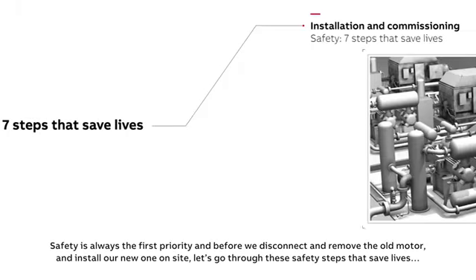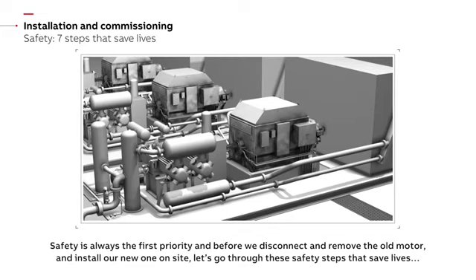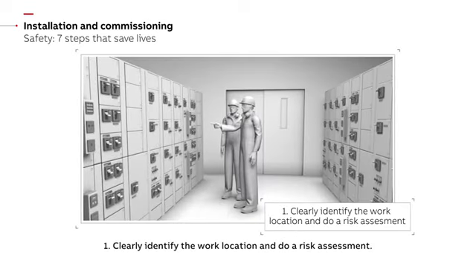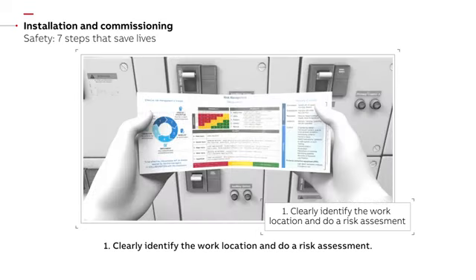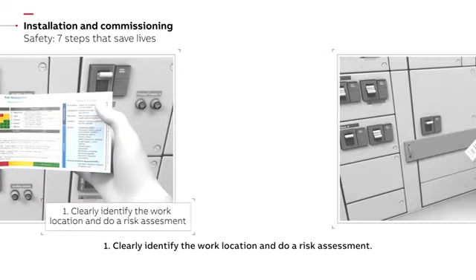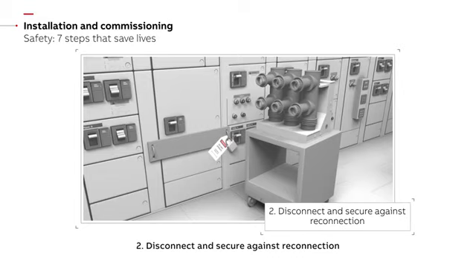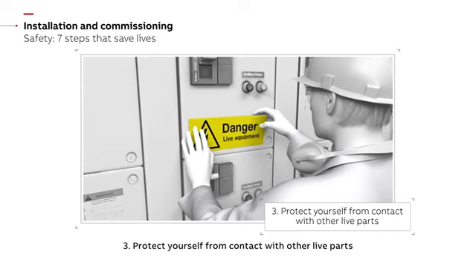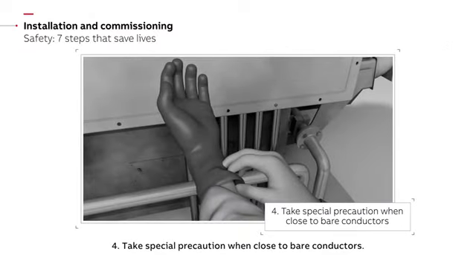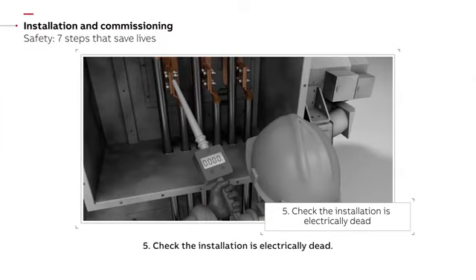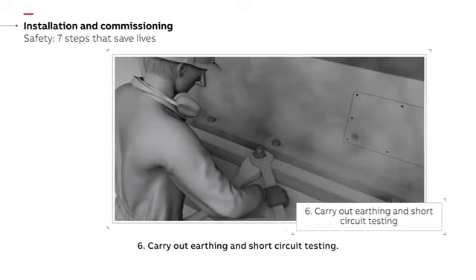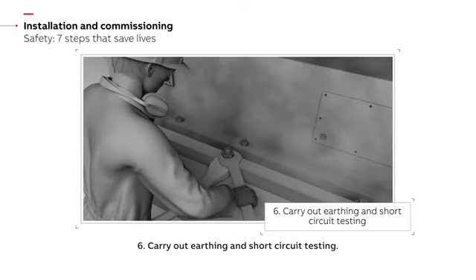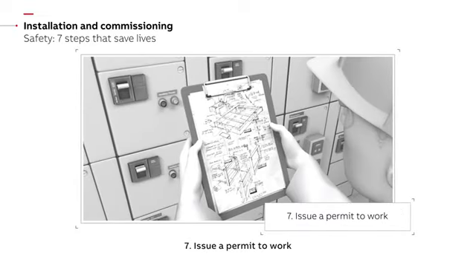Safety is always the first priority, and before we disconnect and remove the old motor and install our new one on site, let's go through these safety steps that save lives. 1. Clearly identify the work location and do a risk assessment. 2. Disconnect and secure against reconnection. 3. Protect yourself from contact with other live parts. 4. Take special precaution when close to bare conductors. 5. Check the installation is electrically dead. 6. Carry out earthing and short-circuit testing. 7. Issue a permit to work.